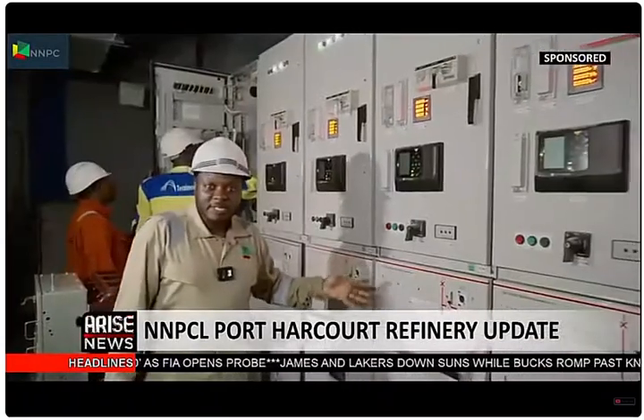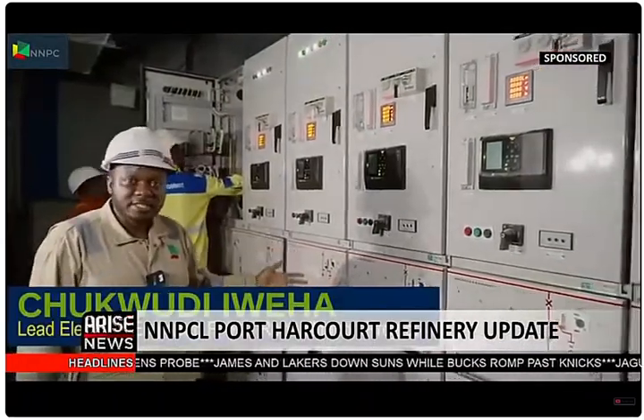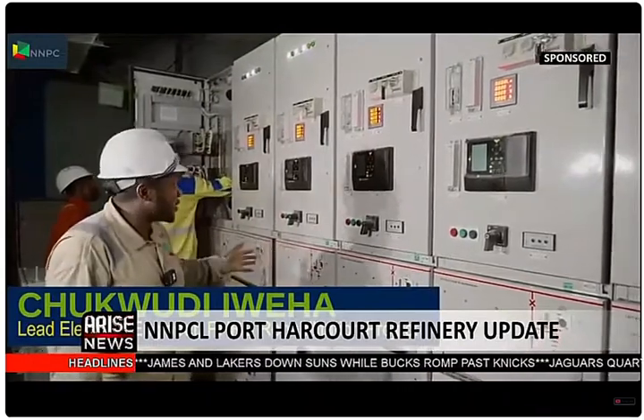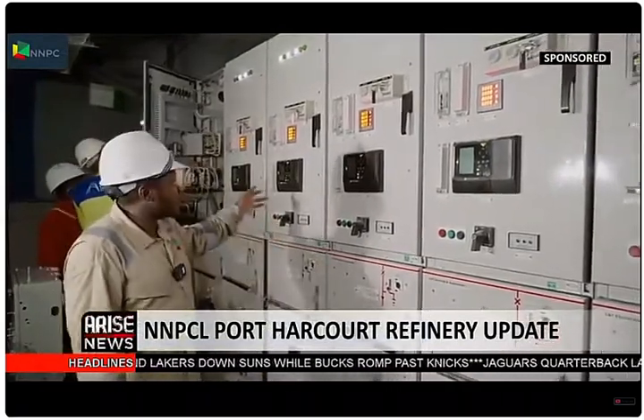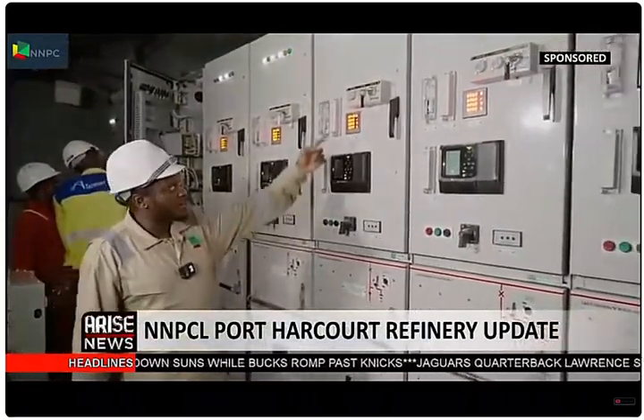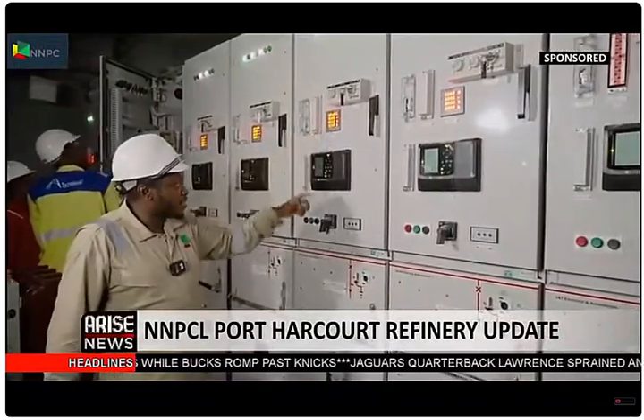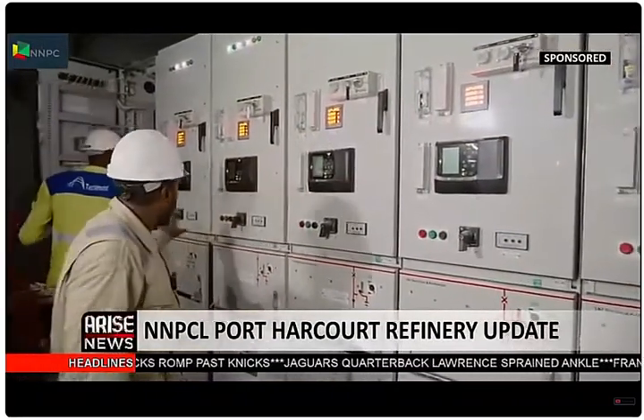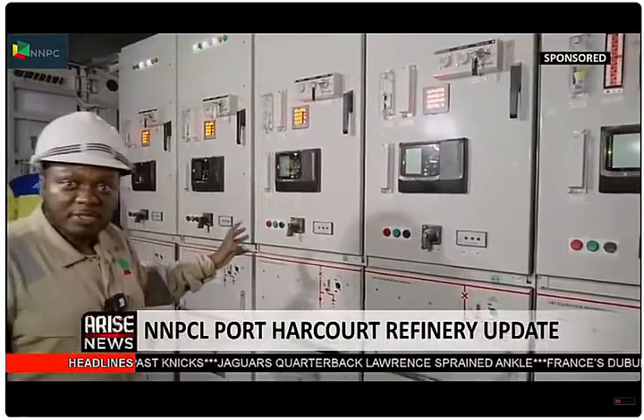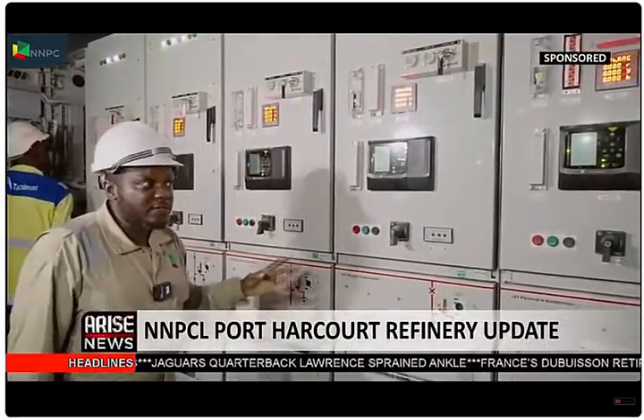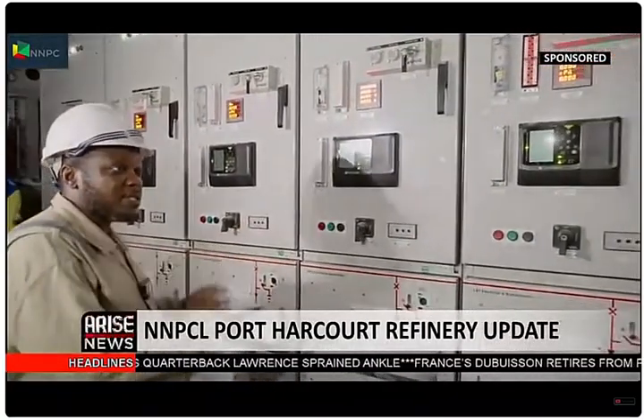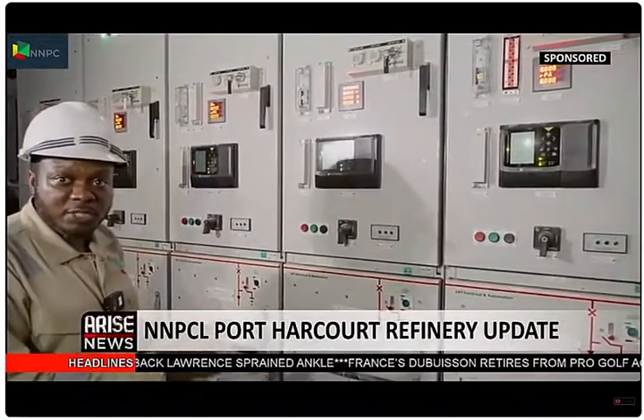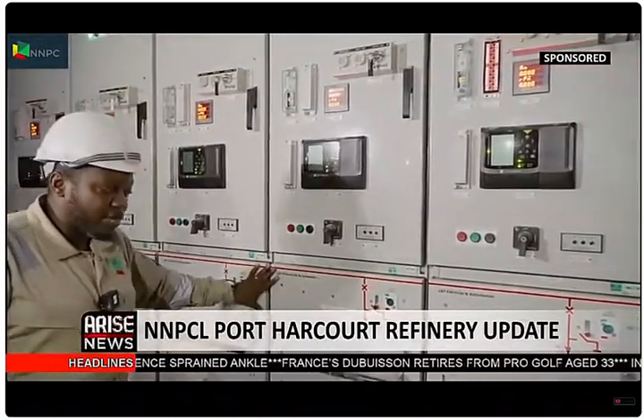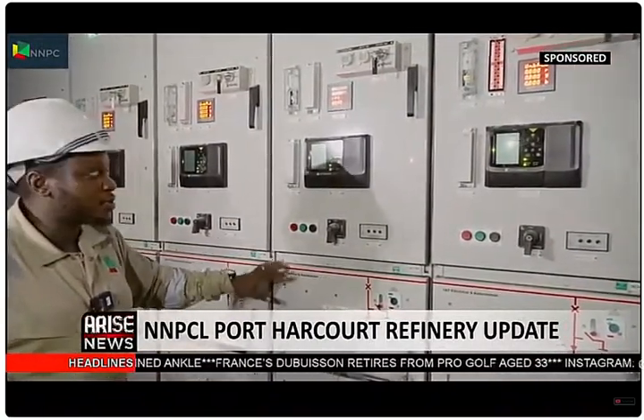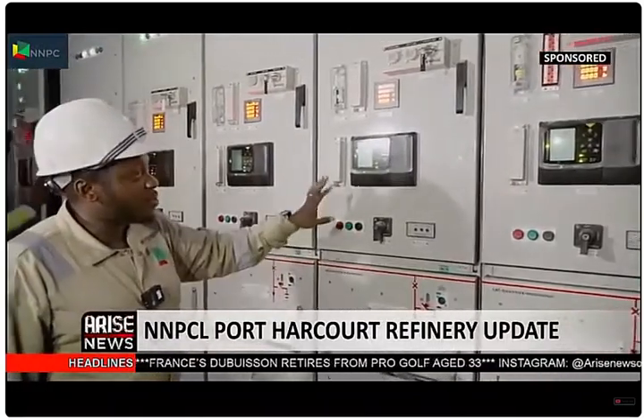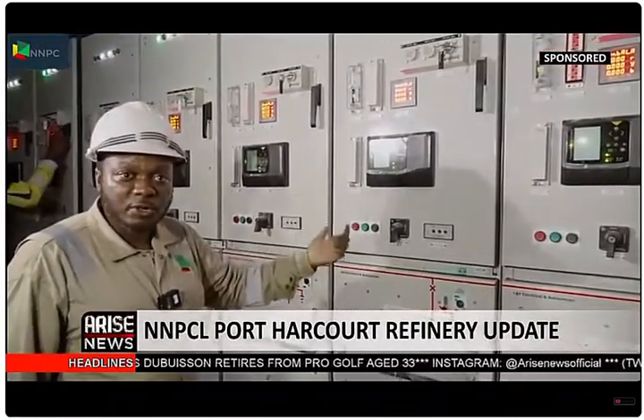We can see we have energized. As I said, we will be energizing in a few weeks. We have energized this particular switchgear, and this indicates the protection relays. You can see the red, yellow, blue, and we are doing some final checks because safety is key to make sure that everything is working. This is the high voltage switchgear with the vacuum circuit breakers. It's a Schneider product. The vendor has come, he has already programmed the HMI, which you saw was on in the other one.